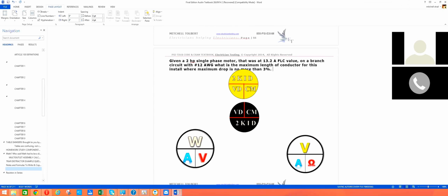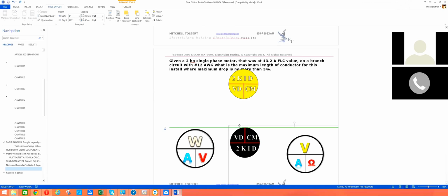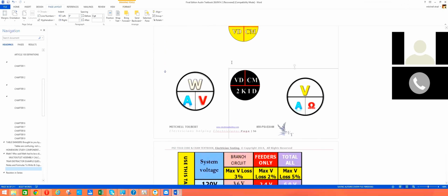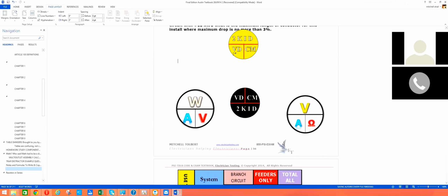Which it's not a code, but it's actually recommended, right? That's right. Yes, it's absolutely. It's not an actual requirement, so to speak. It's more of a by the way, this is a really good idea if you're doing, especially motors or inductive loads, which don't do well with voltage losses. They'll heat up the windings pretty quick on you if you had too much of it.